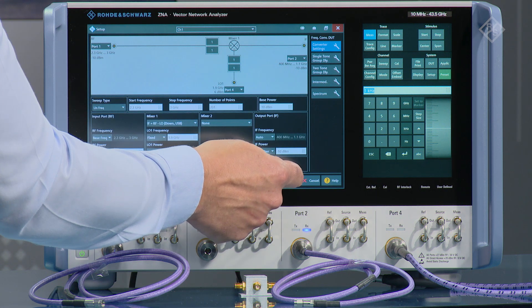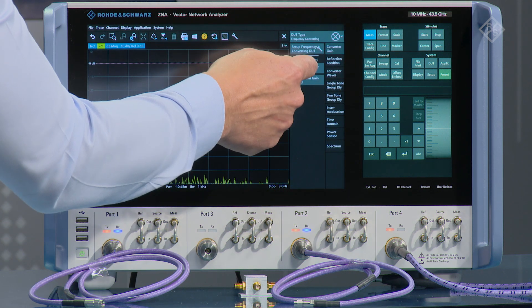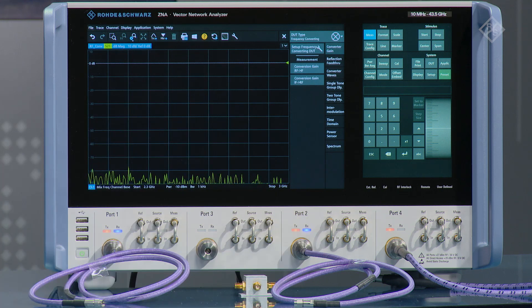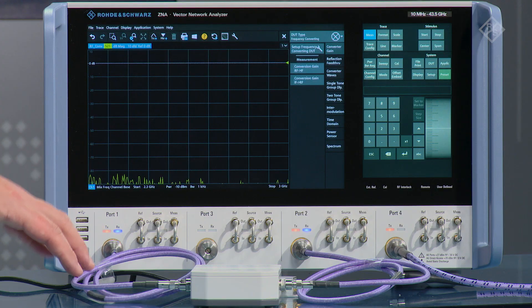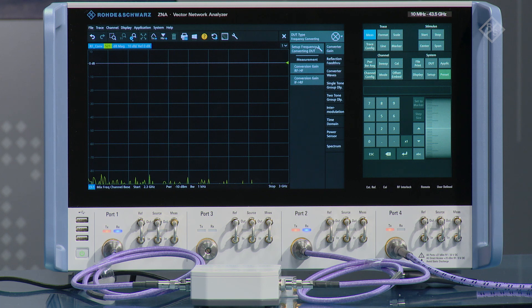Then we can select OK and from the measurement list we can choose conversion gain RF to IF. To perform the calibration, the first step is that we're using an automatic calibration unit. I have this connected between ports one and two. We can initiate the calibration routine.